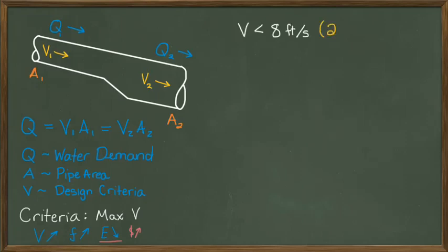So, a common maximum velocity specified within a given water system is 8 feet per second, or 2.5 meters per second. Using this as our design criteria, we can size a given pipeline.